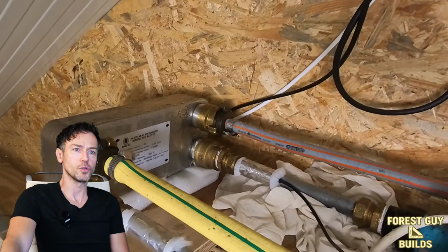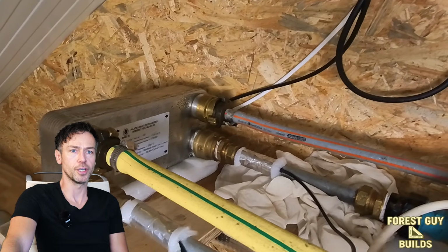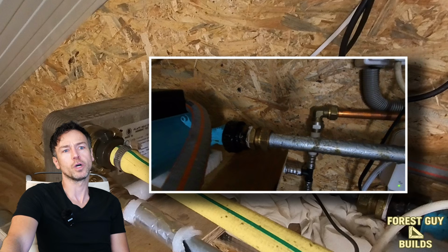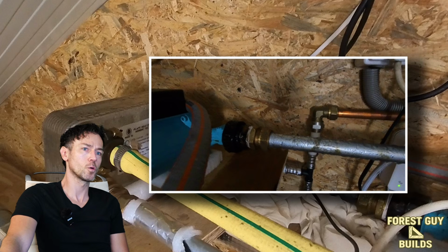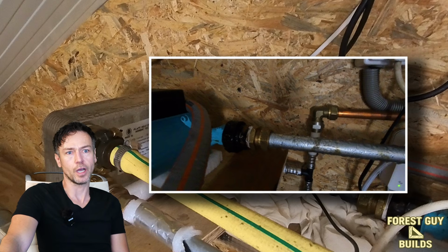One of the important issues you can already see here is condensation. At first I was sending water at around 15 degrees Celsius through the floor circuit, which made the pipes cold enough to create a lot of condensation. For the first day of testing I accepted that and kept a close eye on it to make sure it didn't become a problem.